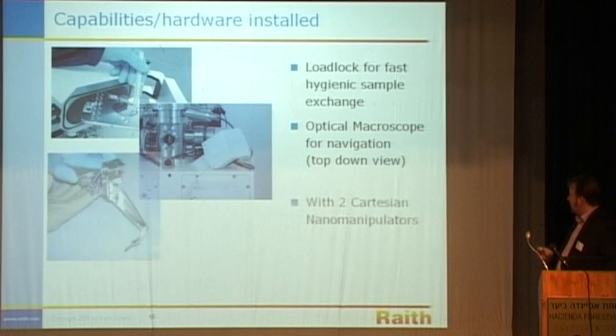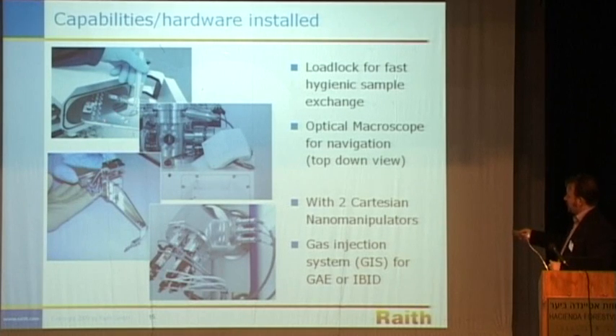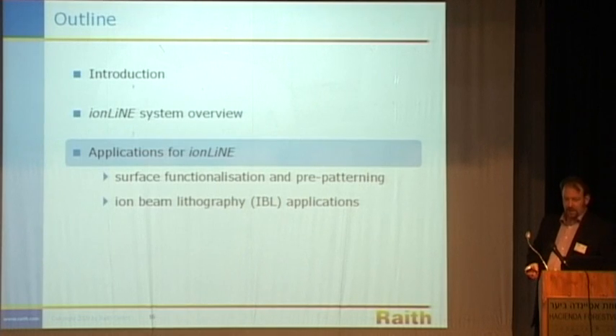The instrument arriving here has the following hardware: a load lock for sample stability, the optical macroscope with the Scheimpflug optical arrangement, two Cartesian nanomanipulators capable of extracting small pieces of sample that have been cut out, or for direct electrical probing of features, or indeed adding voltage or current to a device through an external probe. There's also a gas injection delivery system with five chemistries loaded, allowing deposition and gas-assisted etching using the ion beam.